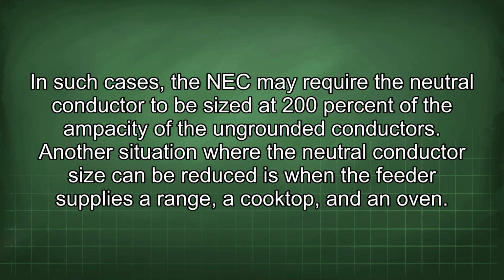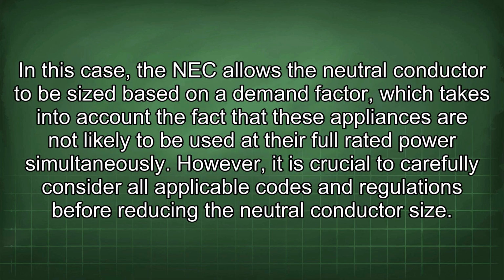Another situation where the neutral conductor size can be reduced is when the feeder supplies a range, a cooktop, and an oven. In this case, the NEC allows the neutral conductor to be sized based on a demand factor, which takes into account the fact that these appliances are not likely to be used at their full rated power simultaneously. However, it is crucial to carefully consider all applicable codes and regulations before reducing the neutral conductor size.